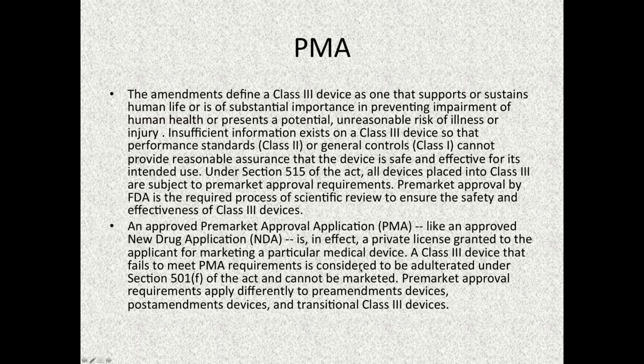But the PMA is like an approved new drug application. It's a private license granted to the applicant for marketing a particular medical device. A Class 3 device that fails to meet PMA requirements is considered to be adulterated under Section 501 of the Act and cannot be marketed. Pre-market approval requirements apply differently to pre-amendment devices, post-amendment devices, and transitional Class 3. This is a very difficult road to go down and requires a commitment.